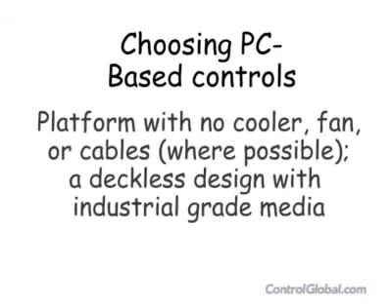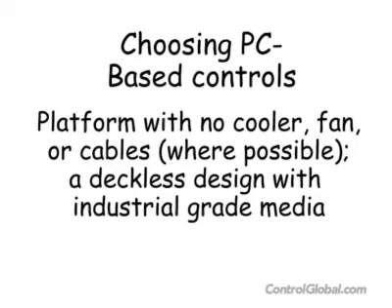Moving parts — even ones like fans, coolers, and disk drives — just do not survive in the industrial environment. The power supply must not require fan cooling. The device should have solid-state memory and solid-state data storage as well. The price of one, two, four, and eight gigabyte USB and CF memory sticks has come down to significantly less than a hundred dollars.